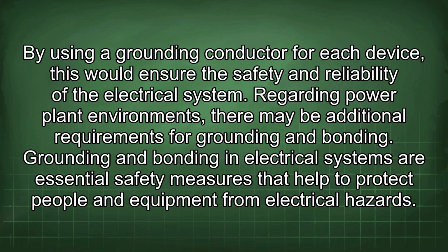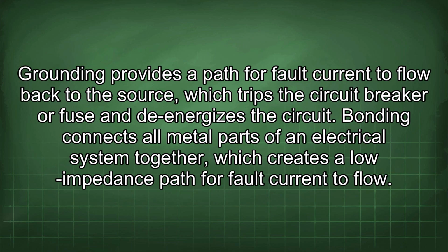Regarding power plant environments, there may be additional requirements for grounding and bonding. Grounding and bonding in electrical systems are essential safety measures that help to protect people and equipment from electrical hazards. Grounding provides a path for fault current to flow back to the source, which trips the circuit breaker or fuse and de-energizes the circuit. Bonding connects all metal parts of an electrical system together, which creates a low impedance path for fault current to flow.